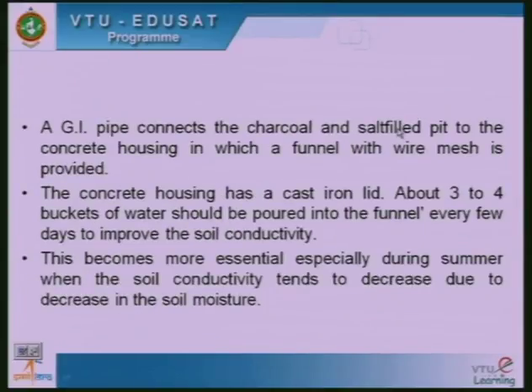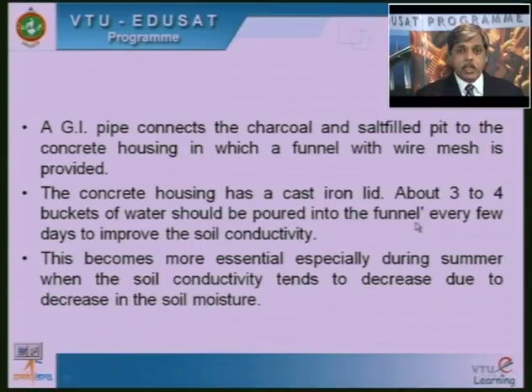Now, the purpose of that is, the concrete housing has a cast iron lid, of course, that is the cover for that. About 3 to 4 buckets of water should be poured into the funnel every few days to improve the soil conductivity. Okay. It is better to keep it wet, so therefore conductivity will be more. This becomes more essential especially during summer, when the soil conductivity tends to decrease due to decrease in the soil moisture. Okay.